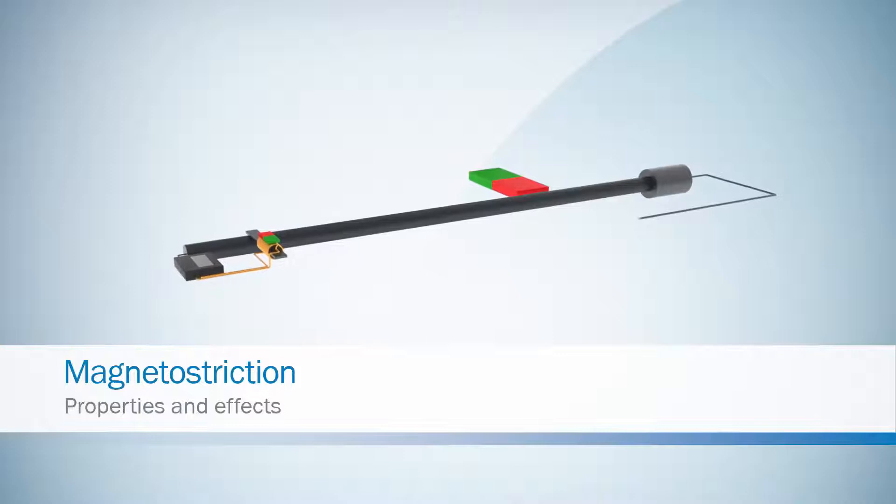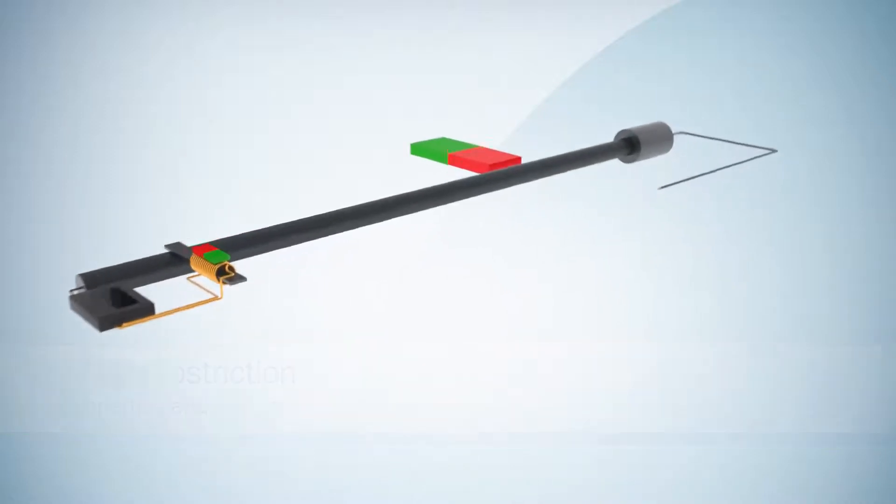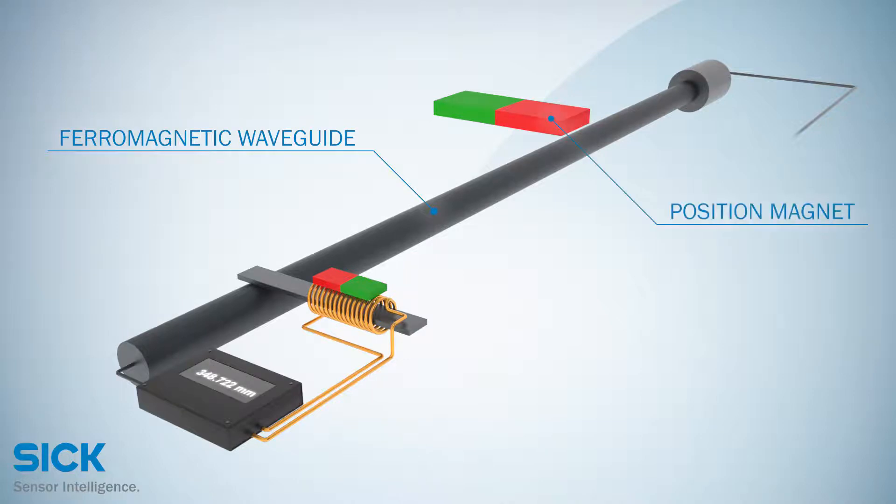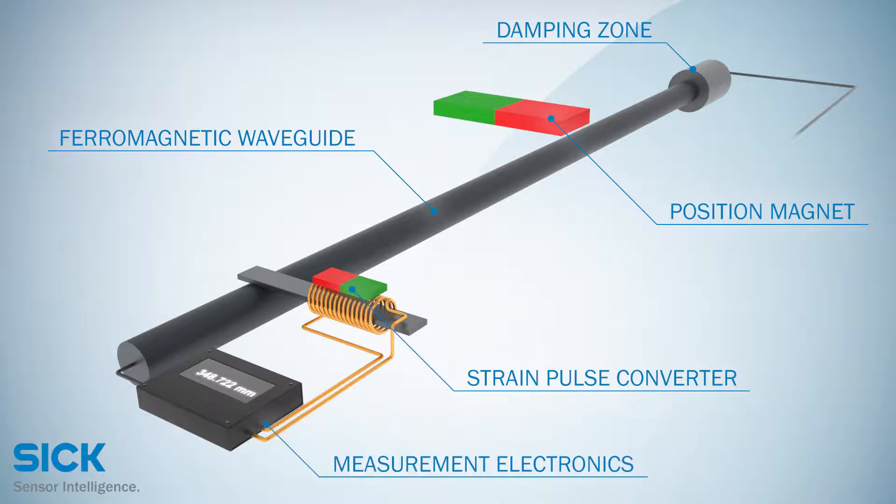SICK linear encoders use the properties and effects of magnetostrictive technology. Magnetostrictive linear encoders consist of a ferromagnetic waveguide, a position magnet, a damping zone, a strain pulse converter, and measurement electronics.